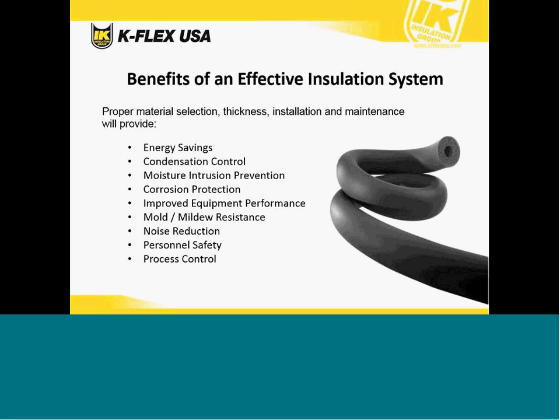We review the benefits of an effective insulation system. With proper material selection, thickness, installation, and maintenance, the insulation system will provide energy savings, condensation control, moisture intrusion prevention, corrosion protection, which are things that we're all familiar with. Things that we may not think of are improved equipment performance, mold resistance on the piping and ductwork, noise reduction, protection from burns on both the hot and cold side, and finally process control, meaning that if we put 40-degree water in one end of the pipe, ideally we want 40-degree water to come out of the other end, and a proper insulation system will help with that.